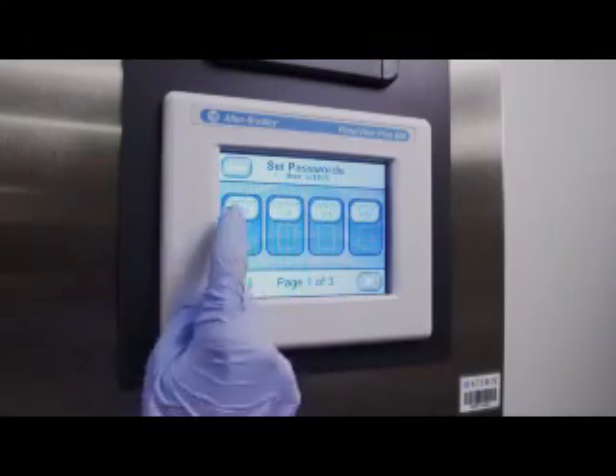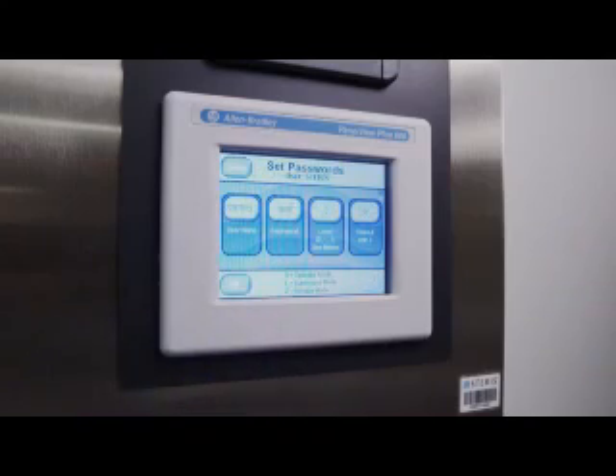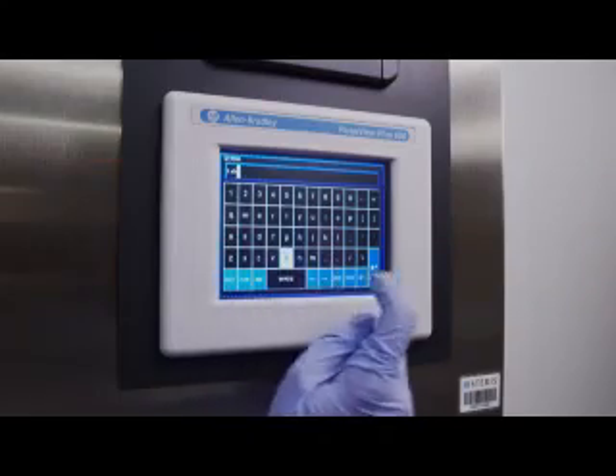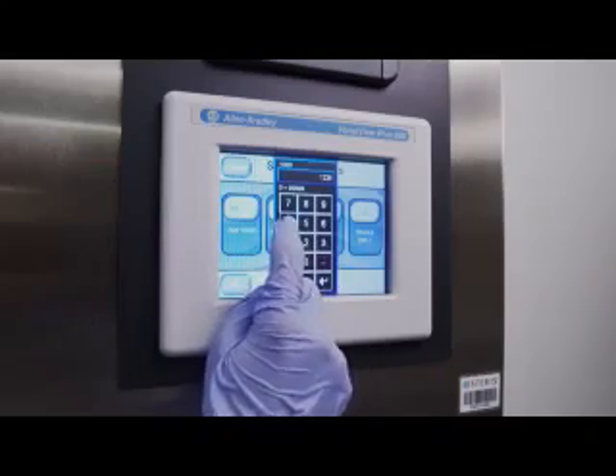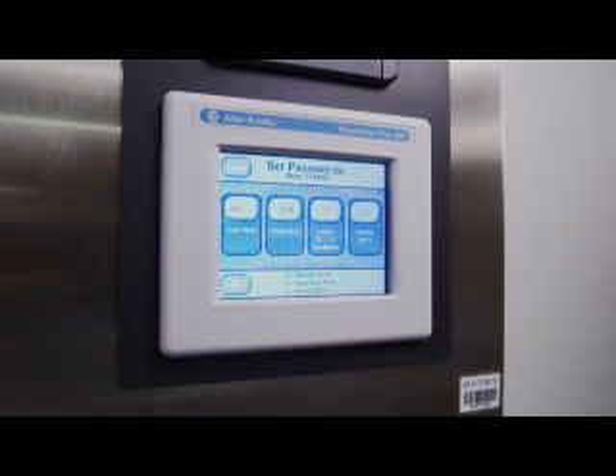To assign a password, choose a blank button from the password screen. From here, you can name the user, set a password, and define their user level and how many minutes until the control times out and requires password input again. The user levels range from operator to supervisor and service.